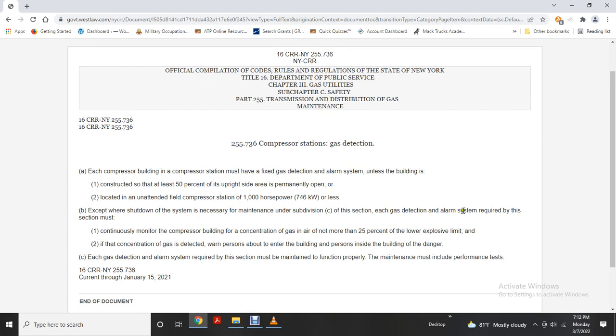Each gas detection and alarm system required by this section must constantly monitor the compressor building and alarm at a gas concentration in air of not more than 25% of the lower explosive limit. When the gas concentration is detected, it must warn persons about to enter the building and persons inside the building of the danger. Each gas detection alarm required by this section must be maintained to function properly. The maintenance must include performance tests.